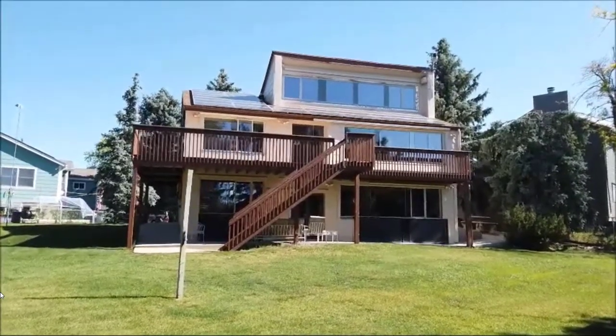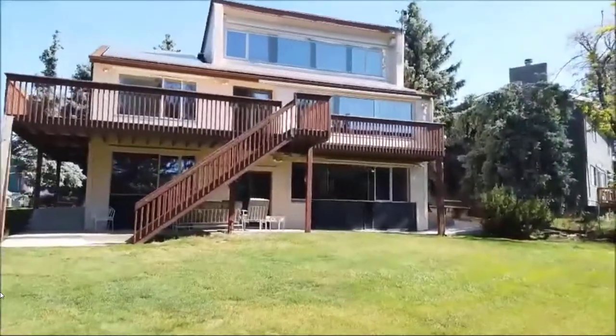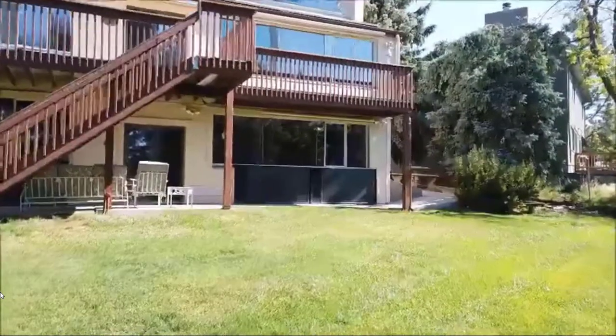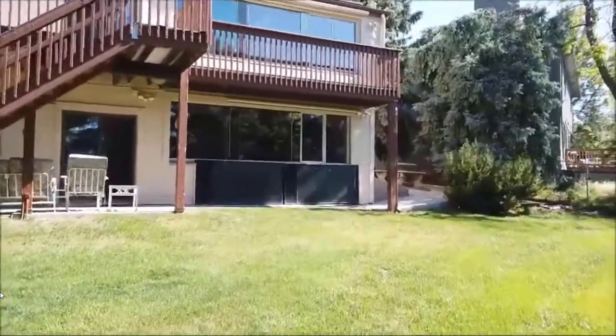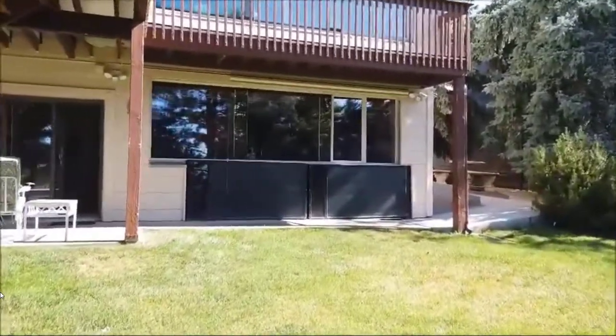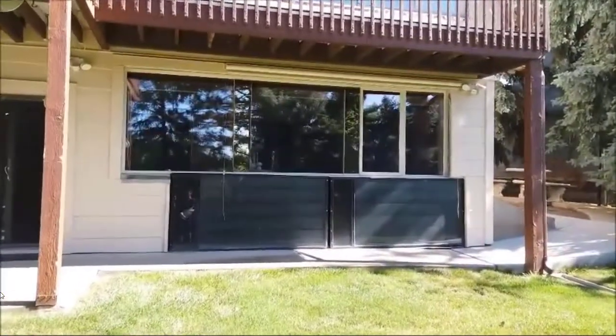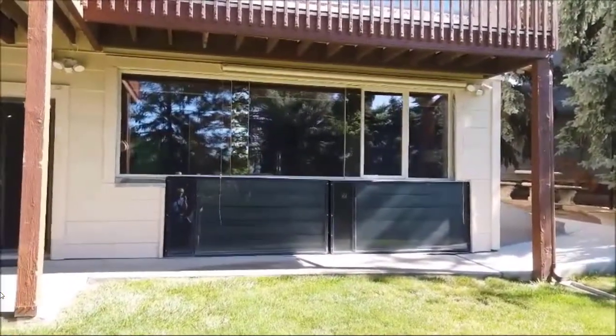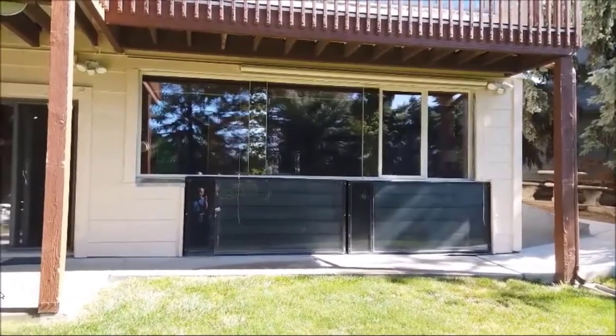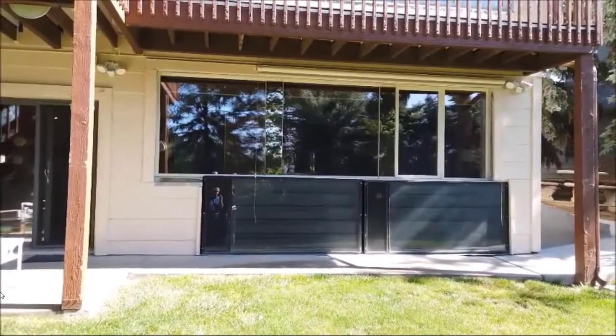As we walked towards the house, I noticed these black panels below the basement windows. Those are solar hot air panels. They bring in the room temperature from one end and it goes across horizontally to exit the other end. In that seven feet, you're going from possibly 68 degrees to putting out 160 degrees on each one of these panels. They're worth 20,000 BTUs per hour. There are seven of these, including on the west-facing side. Of course, they're turned off and that flow is blocked in the summertime.